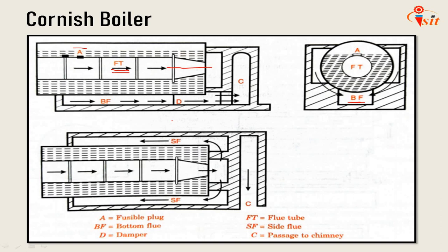The advantage possessed by this type of boiler is that the sediment contained in the water falls to the bottom where the plates are not brought into contact with the hottest portion of the furnace gases. The reason for carrying the products of combustion first through the side flues and lastly through the bottom flue is because the gases, having parted with much of their heat by the time they reach the bottom flue, are less liable to unduly heat the plates in the bottom of the boiler where the sediment may have collected.